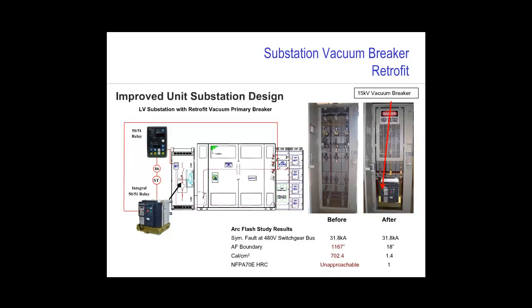We show a photo at the right of the before and after picture, and as you can see, the new vacuum breaker fit neatly into the existing assembly, and the facility decided to leave the load break switch because it was a clear visual indication and could be used as a safety disconnect in the event of a lockout tagout requirement for the entire substation.